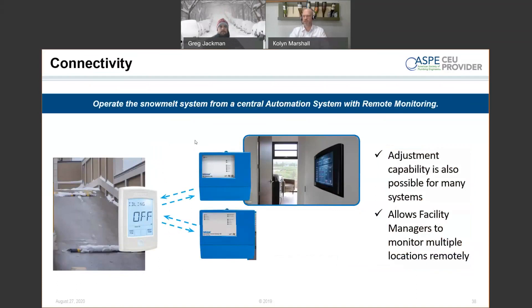User interface is important now — Wi-Fi, apps, and online interface allow you to see what's going on and manage multiple snowmelt systems remotely. For example, you could have a snowmelt at your primary residence and another at a lake lodge. You can set the lodge not to run on snowfall events when you're not there, but on Friday afternoon when you're heading up for the weekend you can punch in the app, turn it on manually, and by the time you arrive any accumulated snow will be cleared. A question came in: clients sometimes request a manual switch for a hydronic snowmelt system. You can use just about any switch — if you're dealing with relays, a 24-volt switch works because you're just engaging a coil on a relay.